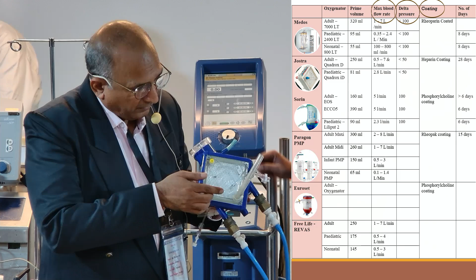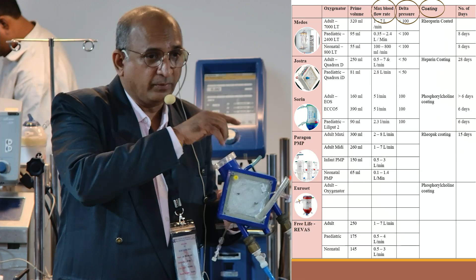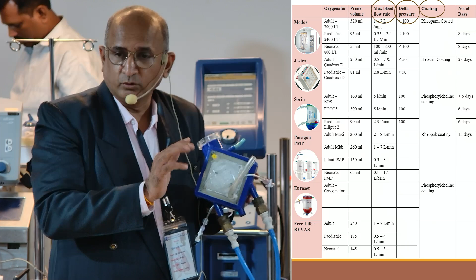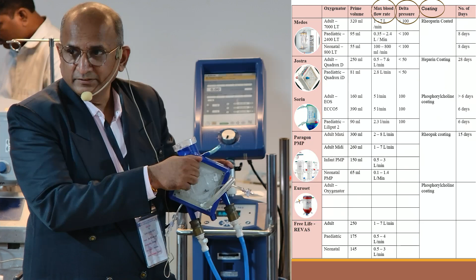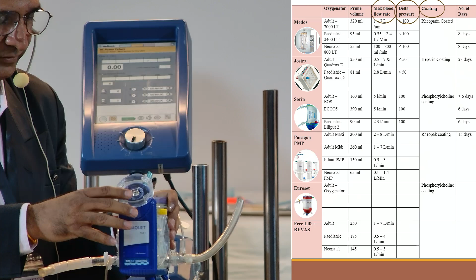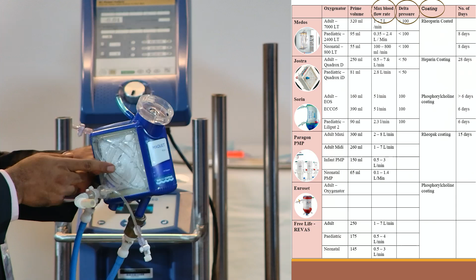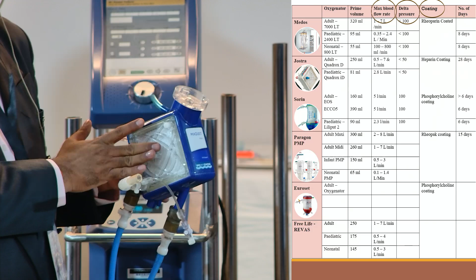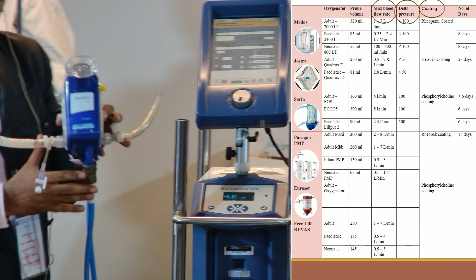Once the blood is moving from here to here, it is flowing across the fibers. So blood is flowing in this direction, across the fibers, while oxygen is flowing through the fibers. So what will happen? There will be gas exchange. And this is surrounded by warm water, so it will warm the blood. Now you can see this knob is for de-airing, when you want to de-air this. So these are the different 6 outlets of the oxygenator. Here you can put a temperature probe to measure the temperature of the circuit or the blood in the circuit. So these are the different parts of the oxygenator. Is this clear? Fine.